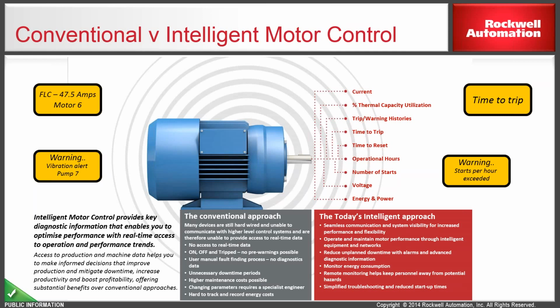In the conventional approach, most of the time we have been using simple starters, and these are still hard wired and unable to communicate with the higher level control systems. That is why they are not able to provide any real-time data or information. They just provide the status of whether it is on, off, or tripped, and finding a fault becomes very difficult.